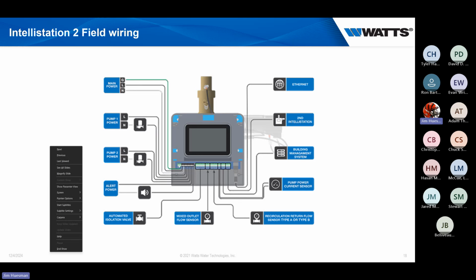So obviously we'll have our main power coming in. They've also given us power not just for one pump, but for two pumps. So if you want to control your circulation pump and have your control box actually control it, we have the option now to control up to two different recirc pumps. We have our alert power, and we've also added automated isolation valves. If we need these in the system, we're able to wire those up into our control box and save a bunch of extra equipment.